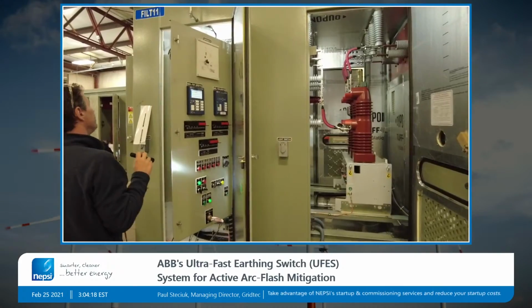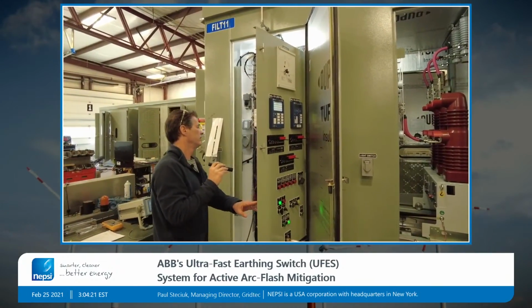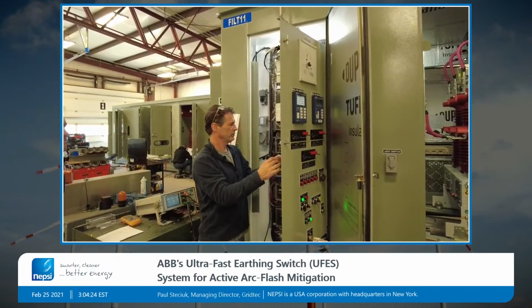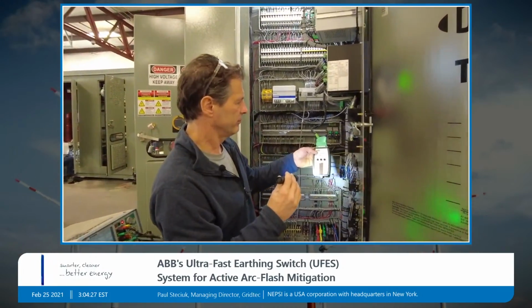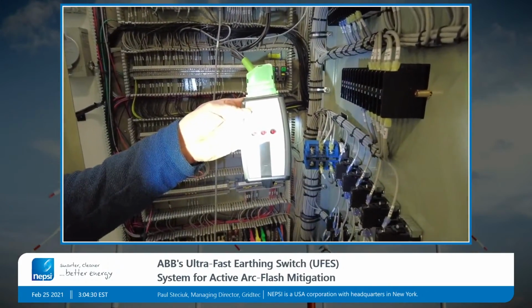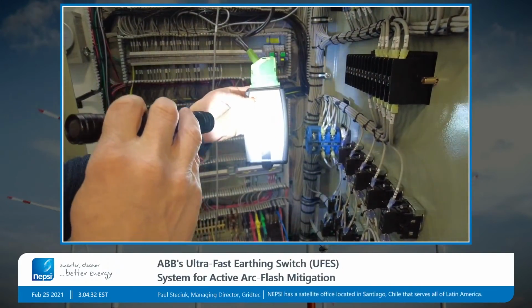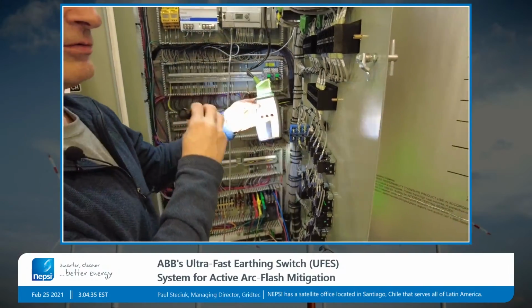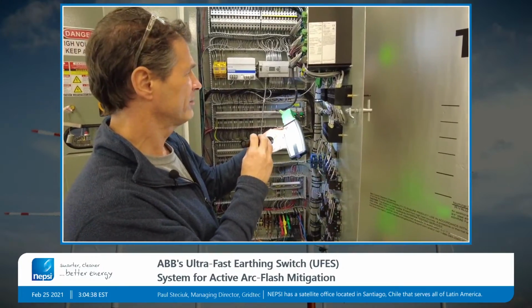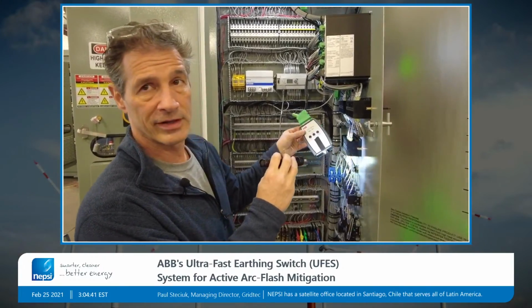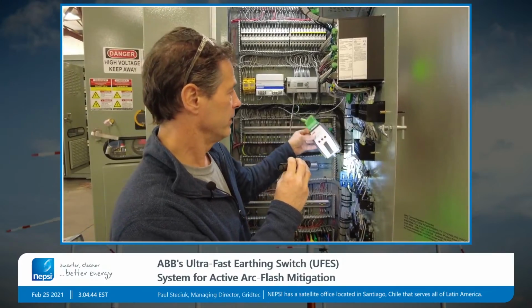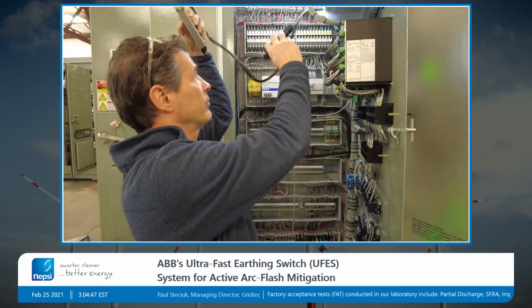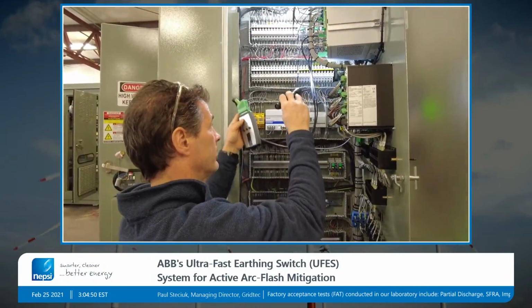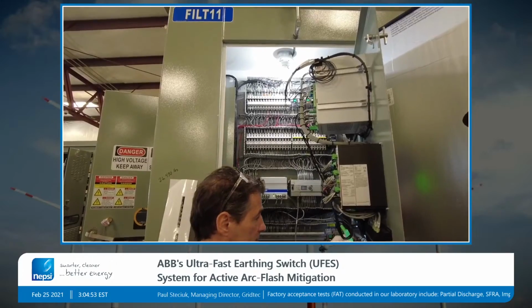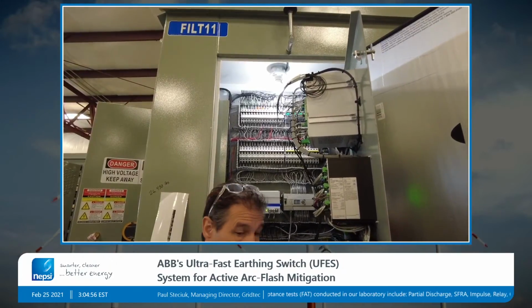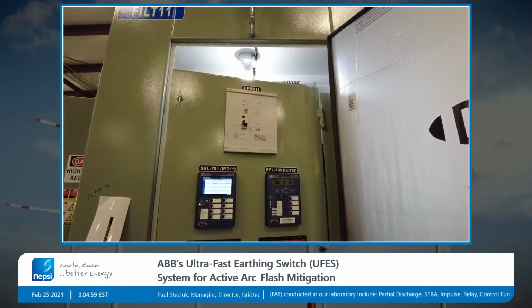Can you talk about how the testing process works when you're at the factory? For testing, we basically have a small test instrument. We connect this to the equipment. This defines what it's like connecting the bottles up during normal operation. So we're taking out the relay, telling the relay that the bottles are connected, but they're not connected. That's what this device is doing. They're connected to the primary switching element rather than the actual device being set up, where you could possibly falsely operate those elements.